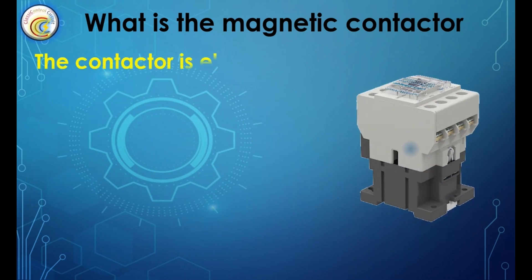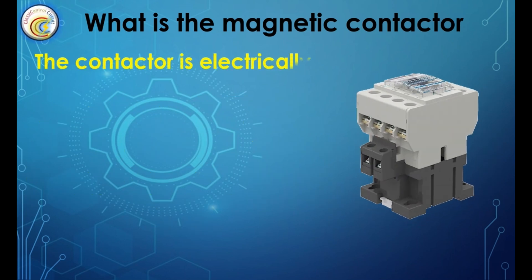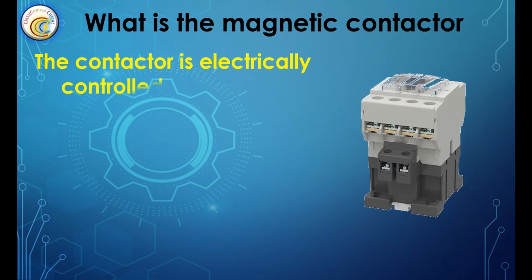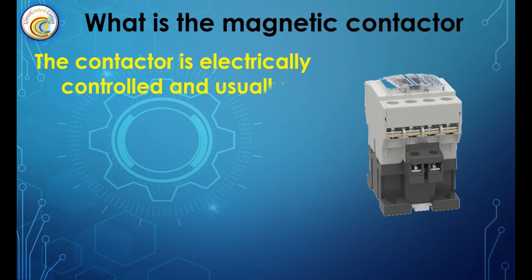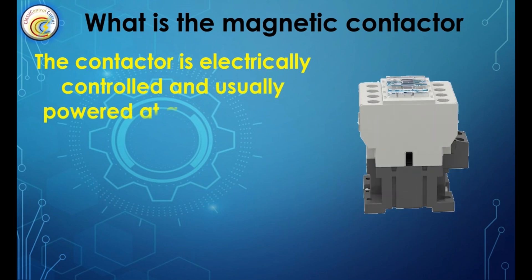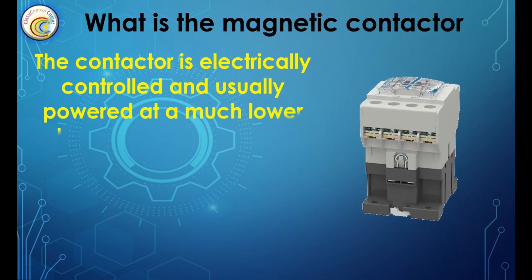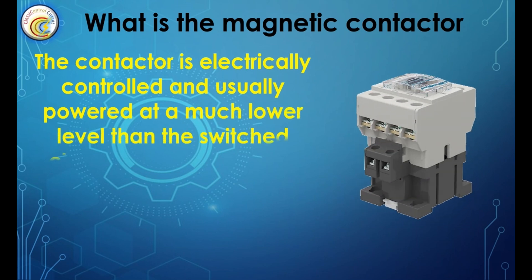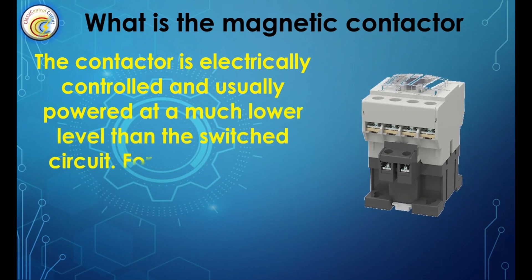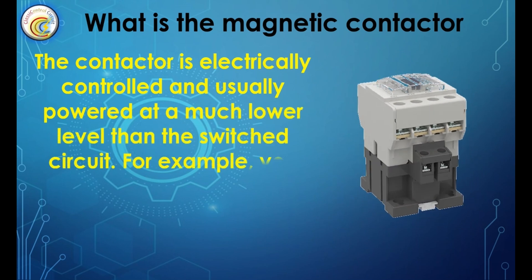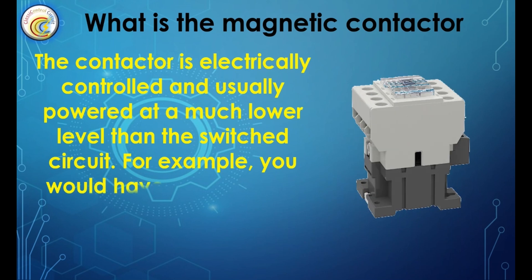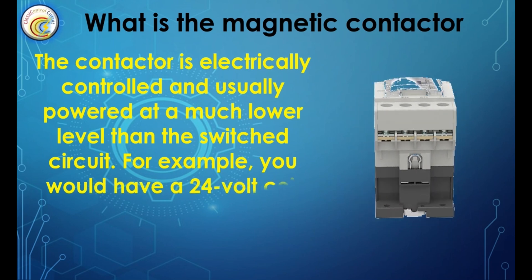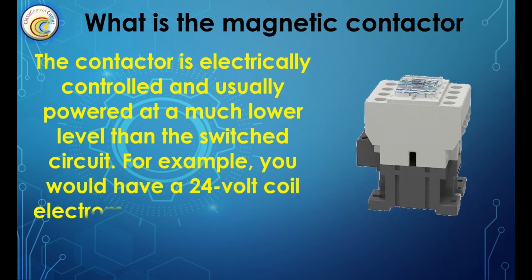The contactor is electrically controlled and usually powered at a much lower level than the switched circuit. For example, you would have a 24-volt coil electromagnet that controls a 230-volt motor switch.